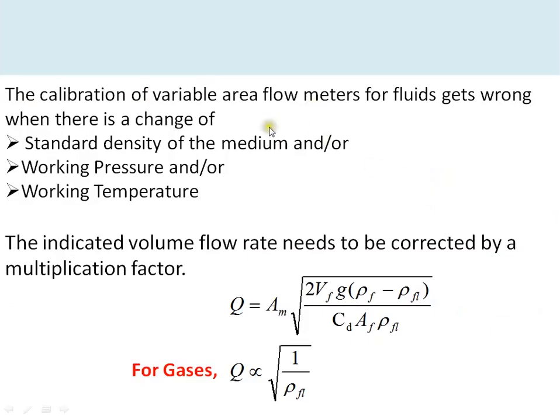Calibration of variable area flow meters can go wrong when there is a change in density of the medium. If the meter is calibrated for water or air and then used for another medium, there is an error that must be corrected with correction factors. Changes in density, working pressure, and working temperature — especially for gases — affect the flow reading. The indicated volumetric flow rate must be corrected by a multiplication factor whenever any of these three parameters change.